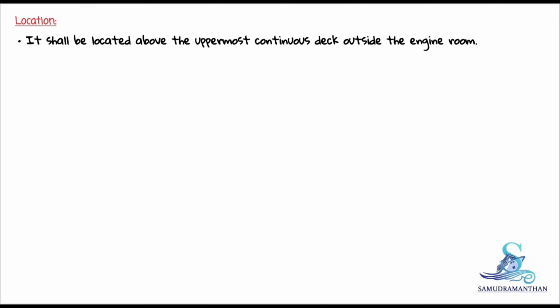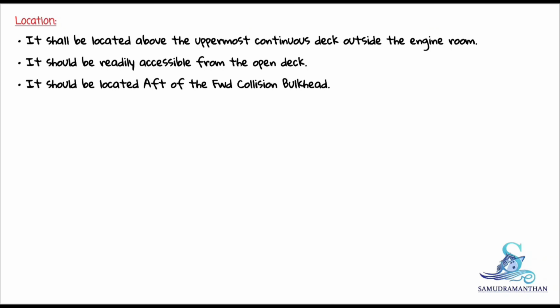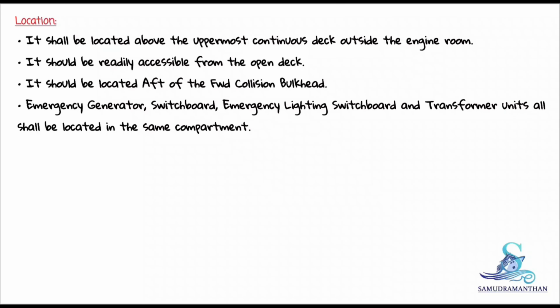Location: it shall be located above the uppermost continuous deck outside the engine room. It should be readily accessible from the open deck. It should be located aft of the forward collision bulkhead. Emergency generator switchboard, emergency lighting switchboard and transformer units all shall be located in the same compartment.